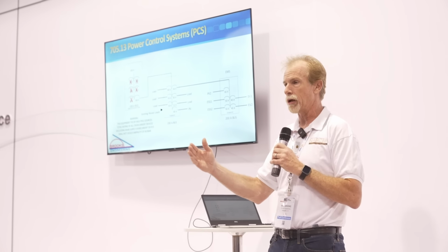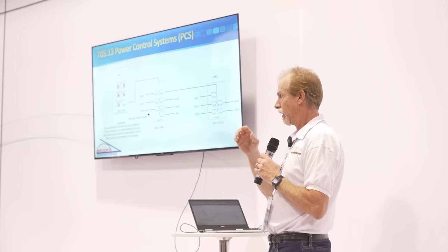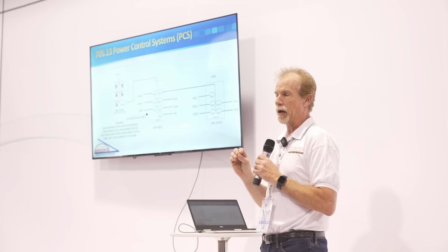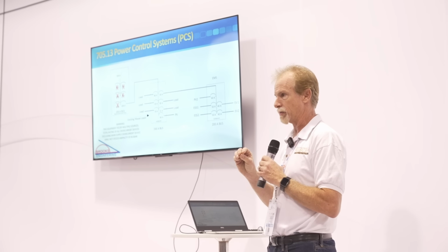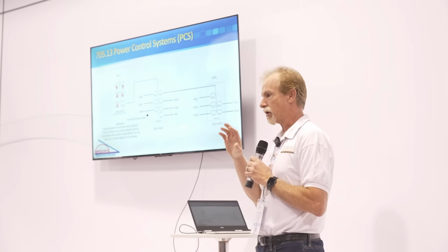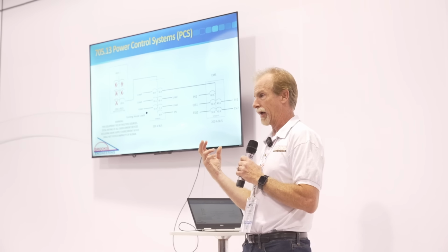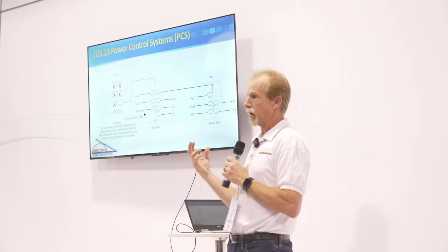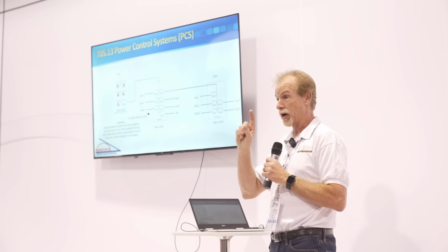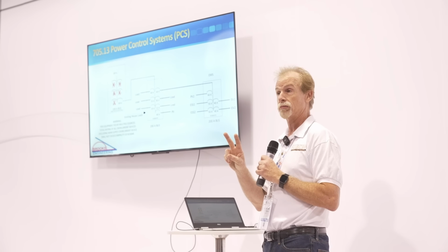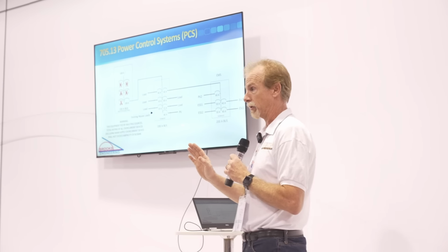But let's just say you use a little bit of that. You can charge your battery with it, things like that, and you can source power back out of it. That 100 amp connection is way bigger than we've been taught to think it is. We think of a 100 amp service as being a really small service. And the answer is, once you start applying these other technologies, PV and energy storage, to that 100 amp service, it looks way better than a 100 amp service. I actually have run my house, a 4,000 square foot house, on a 100 amp service for 2 years. Never had a problem. So it's totally possible.